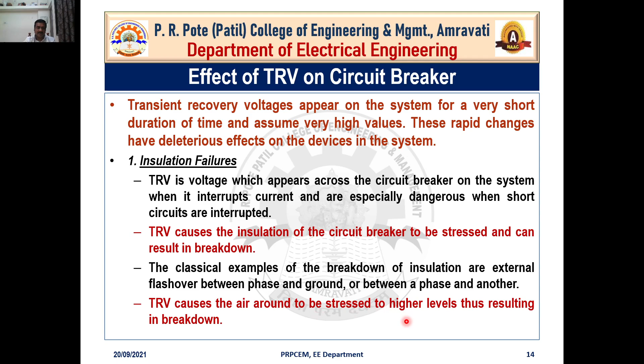Now, classical examples of this breakdown of insulation are external flashover between phase and ground, or between one phase and another phase. These are examples representing that TRV mainly affects the insulation of the circuit breaker. Also, TRV causes the air around to be stressed, because the transient recovery voltage basically carries energy, and this will heat up the air in the atmosphere inside the circuit breaker, and that way it will be stressed to a higher level, so there is a possibility of breakdown also.